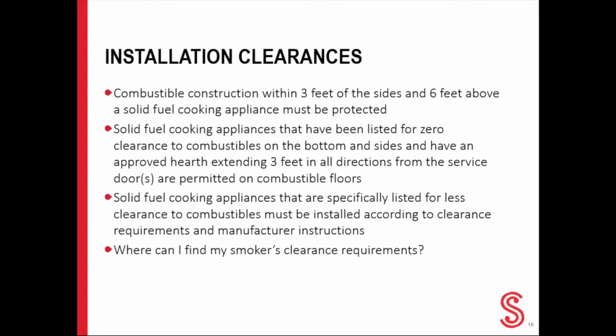Solid fuel cooking appliances that have been listed for zero clearance to combustible on the bottom and sides, with an approved hearth extending 3 feet in all directions from service doors, are permitted to be used on combustible floors. Solid fuel cooking appliances that are specifically listed for less clearance to combustible are permitted to be installed in accordance with the requirements of the listing and the manufacturer's instructions.